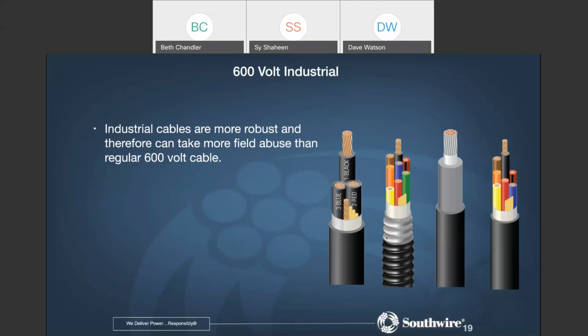Not to say that those products aren't good. It's just that, while the inners are no different than what Dave talked about, inners are XHHW, for instance, but it has an overall PVC jacket. You can see this is a tray cable, whereas it can take a little bit more ruggedness. This looks like an MC cable, but it has a jacket. Again, it's control, and we can put power. Again, it can take more ruggedness.